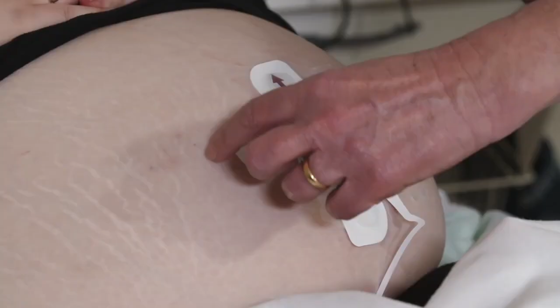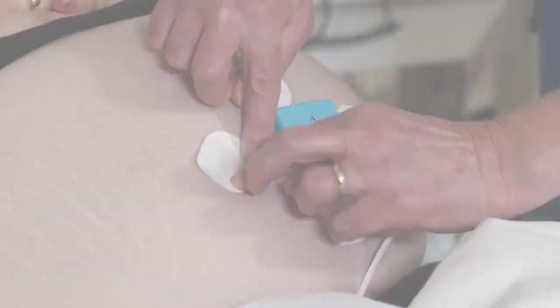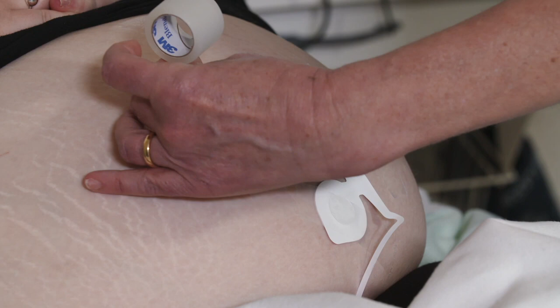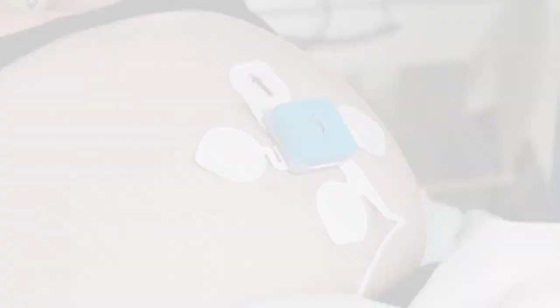Electrode disconnection. The pod will know if 1 or more electrodes have become detached. If it is only 1 electrode, the Novii display will alert you as to which electrode has become detached. Locate the detached electrode and stick the electrode back down over the same spot and secure with micropore tape. When more than 1 electrode has become detached, the pod is unable to determine which electrodes are at fault, and you will need to investigate all the electrodes to locate the problem. Or you can end the monitoring session and then start again. The skin electrode check screen will then identify the problem electrodes.